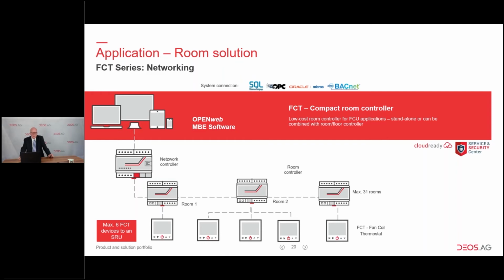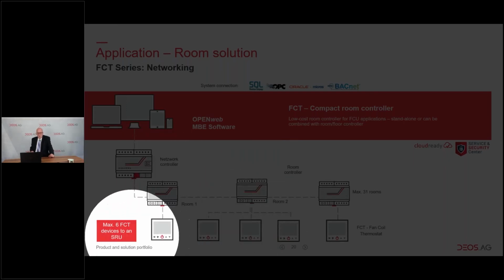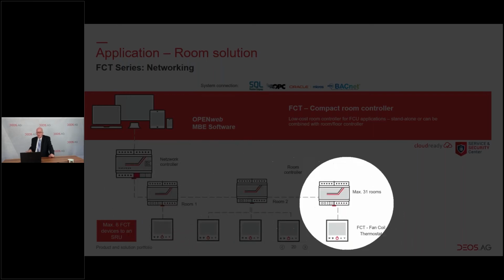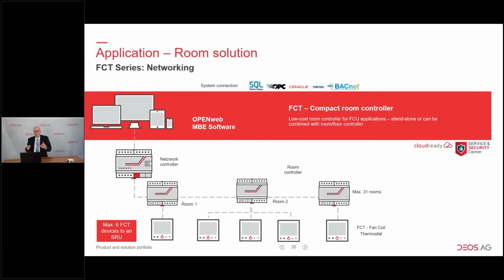We use fan coil thermostats for this requirement, communicating over the Modbus protocol, so we can integrate 6 devices to one room controller. In summary, on this line we have up to 31 room controllers, and with 6 FCTs, for example in a hotel suite with a living room, bathroom, and small conference room, we can place a fan coil thermostat in each room of the suite.